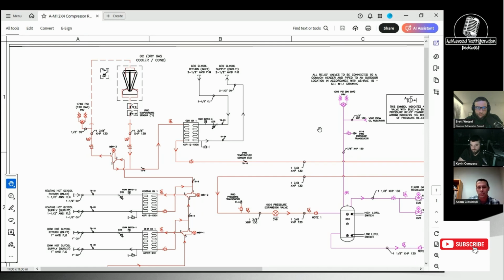The pressure increases. You go off on fast recovery, so all the fans start. You unsplit, and then you get this cycling effect. So if you're going to do it, you have to do it in a fashion where you're pretty low in ambient and you're pretty lightly loaded on those gas cooler fans. So when you do one split, it's not such an upset. If you do it at 40 degrees, that's too high. If you do it colder, at 0 degrees, or basically at the very bottom, you can ride through it, but it's challenging.